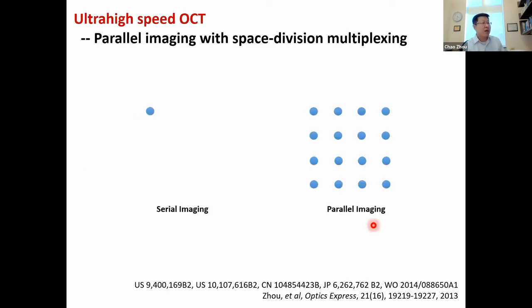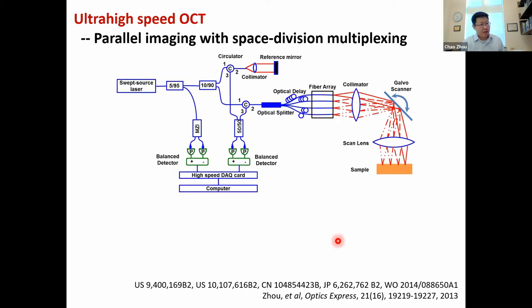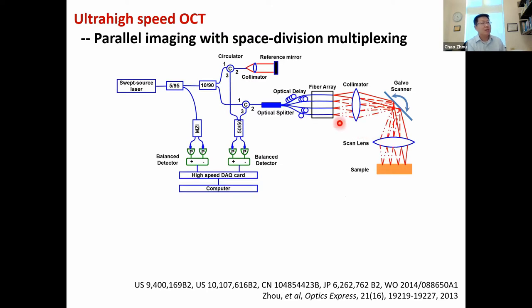Okay, so our approach is instead of using a single laser beam to scan on the eye back and forth to finish it, we can use many imaging channels to acquire the data simultaneously. So this is done through something we call space division multiplexing OCT. And we actually got multiple patents in the US and other countries. And we demonstrate that this approach works. And technically what happens is that we're using a swept source OCT system. And the innovation comes in the sample arm of the OCT setup.